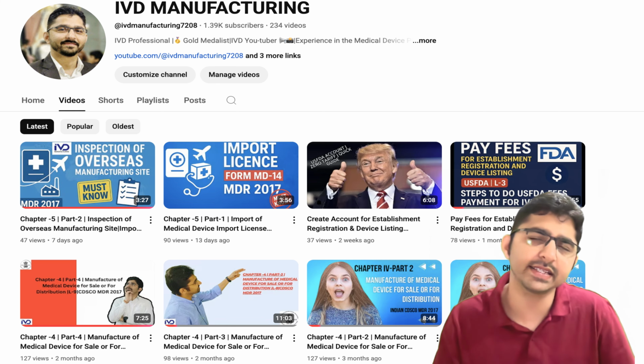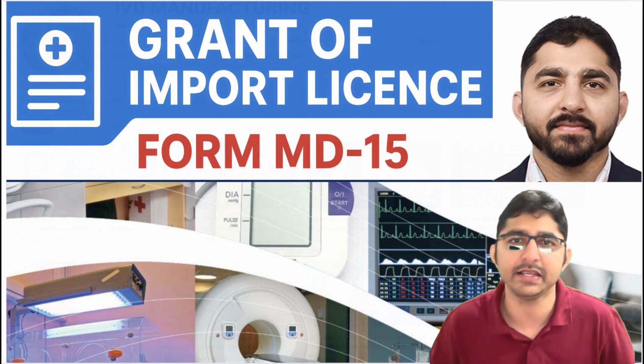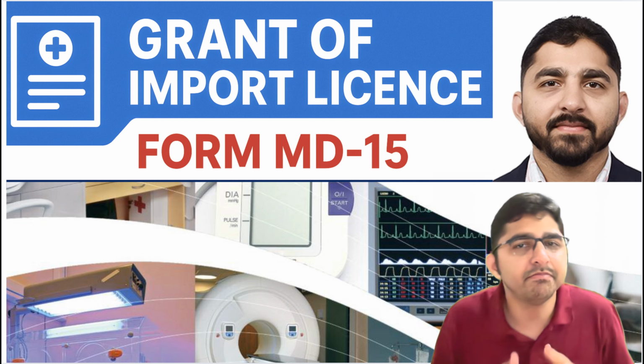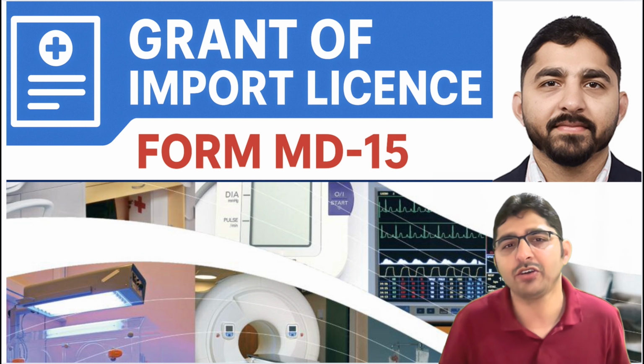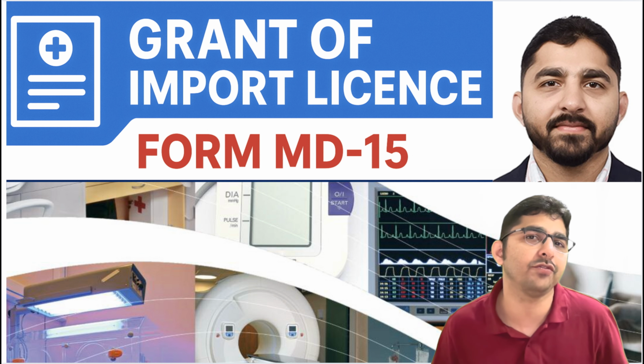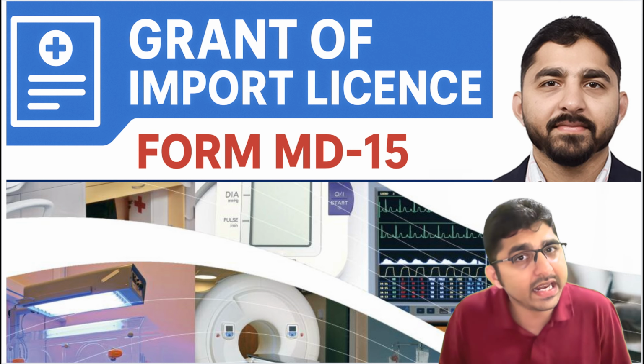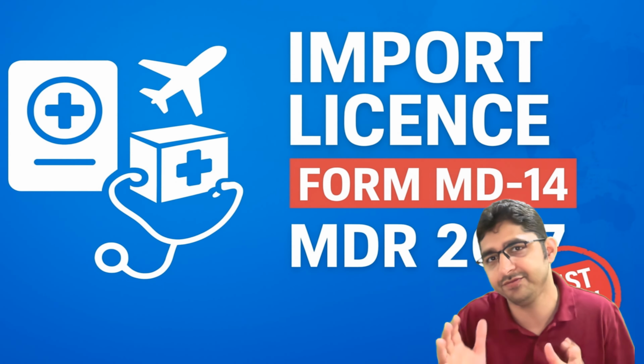So today we'll be discussing Chapter 5, which is import of medical devices. But we'll be talking mainly about a specific topic, which is the grant of import license on Form MD15, whereas you'll be filing the application in Form MD14. So if you are applying for the import license for medical devices in India, then under Rule 36 of MDR 2017, the CLA, after reviewing your application, will decide whether to grant or reject this license. So in this video, let's break down the process, the timelines and conditions for the approval.